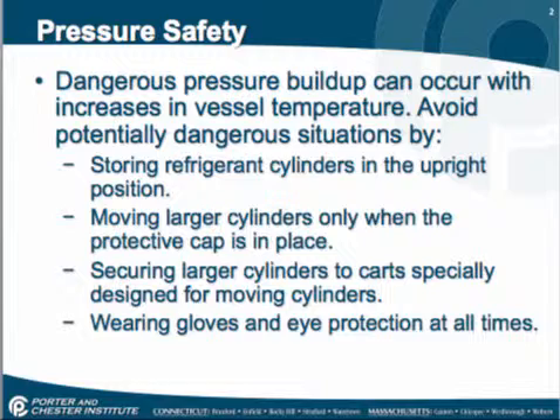A couple things we need to talk about: refrigerant cylinders are stored upright, valve stems up. Make sure you move any large cylinders with a protective cap in place. And when you're using nitrogen in the larger cylinders, the ones that are about as tall as you are sometimes, put them on a cart and secure them to a cart specifically designed for moving cylinders.